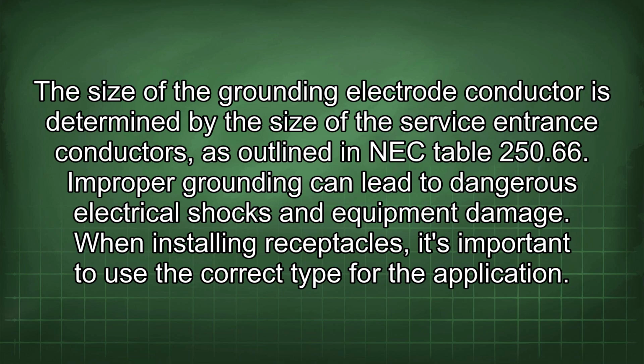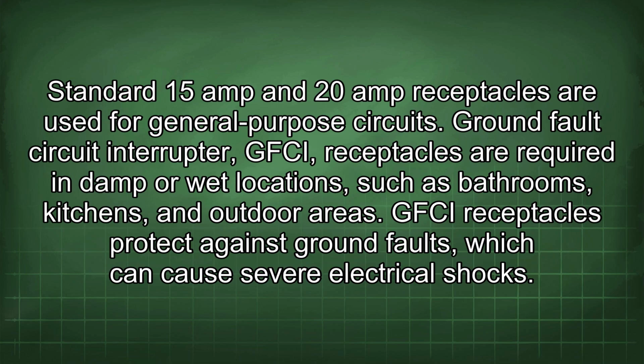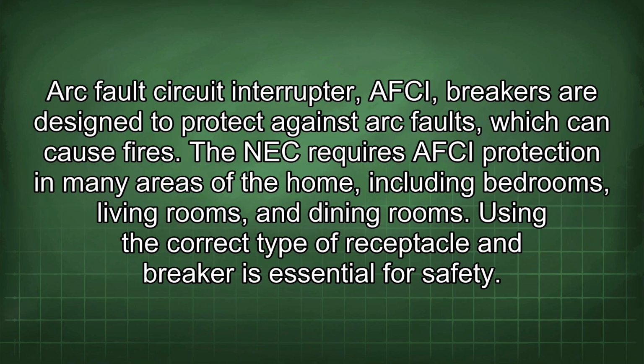When installing receptacles, it's important to use the correct type for the application. Standard 15 amp and 20 amp receptacles are used for general purpose circuits. Ground fault circuit interrupter (GFCI) receptacles are required in damp or wet locations such as bathrooms, kitchens, and outdoor areas. GFCI receptacles protect against ground faults, which can cause severe electrical shocks. Arc fault circuit interrupter (AFCI) breakers are designed to protect against arc faults, which can cause fires. The NEC requires AFCI protection in many areas of the home, including bedrooms, living rooms, and dining rooms. Using the correct type of receptacle and breaker is essential for safety.